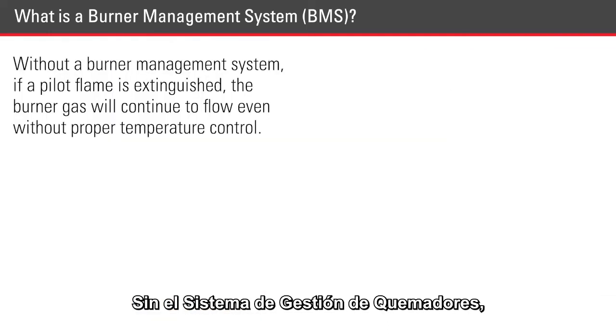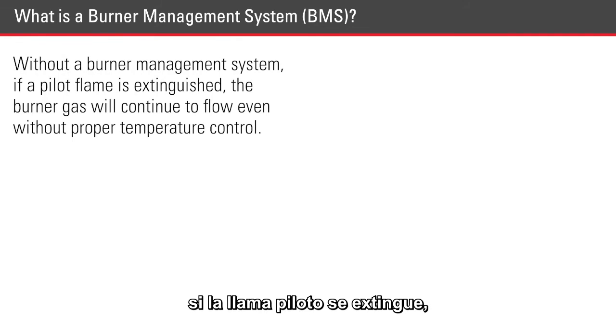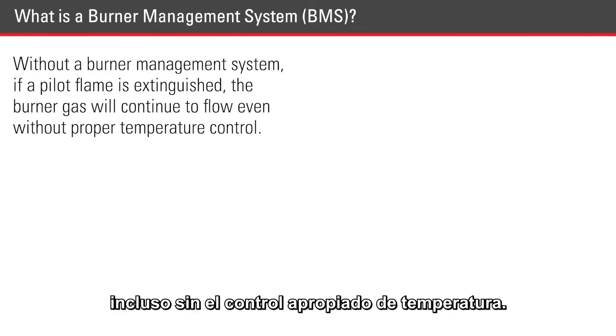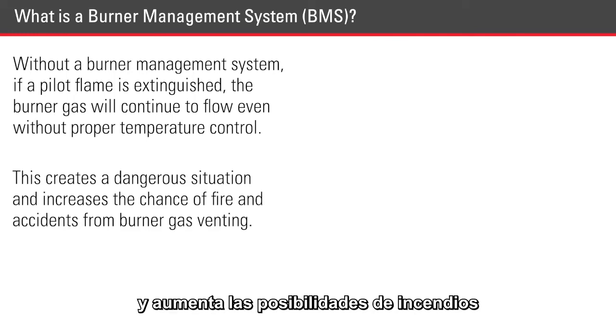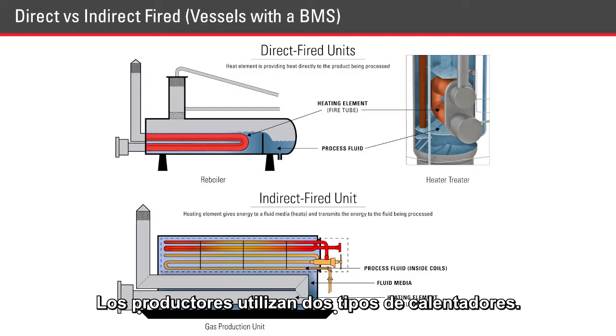Without a burner management system, if a pilot flame is extinguished, the burner gas will continue to flow even without the proper temperature control. This creates a dangerous situation and increases the chance of fire and accidents from the burner gas venting. There are two kinds of heated vessels producers use.